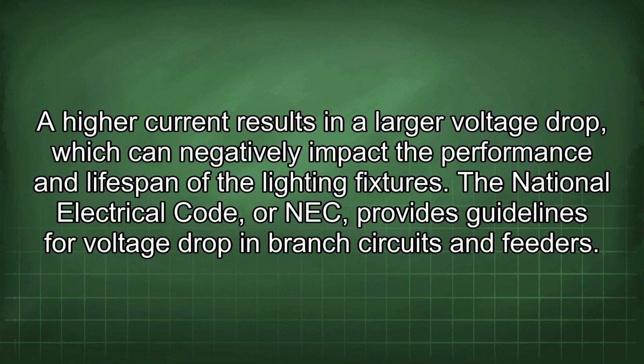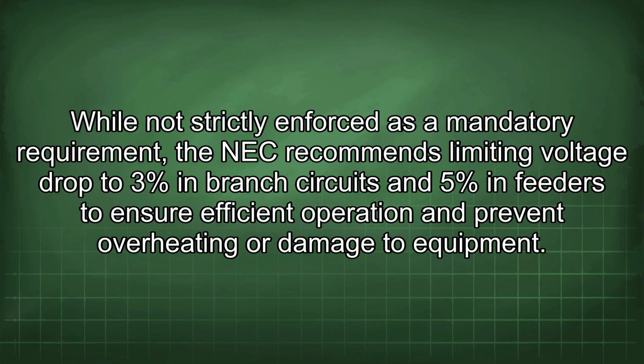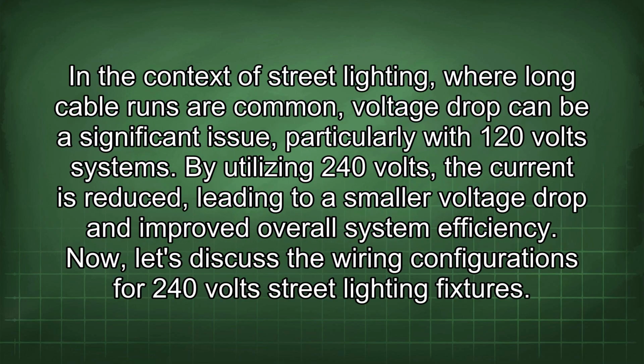of the lighting fixtures. The National Electrical Code, or NEC, provides guidelines for voltage drop in branch circuits and feeders. While not strictly enforced as a mandatory requirement, the NEC recommends limiting voltage drop to 3% in branch circuits and 5% in feeders to ensure efficient operation and prevent overheating or damage to equipment. In the context of street lighting, where long cable runs are common, voltage drop can be a significant issue, particularly with 120 volt systems. By utilizing 240 volts, the current is reduced, leading to a smaller voltage drop and improved overall system efficiency.